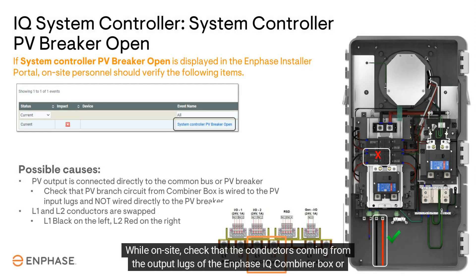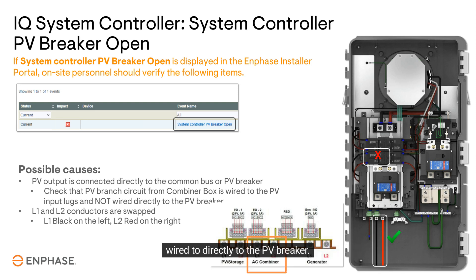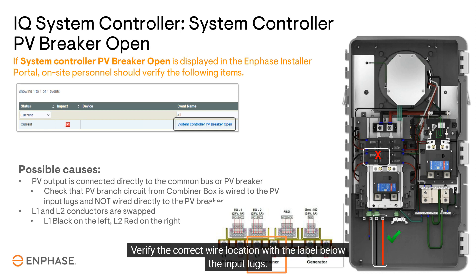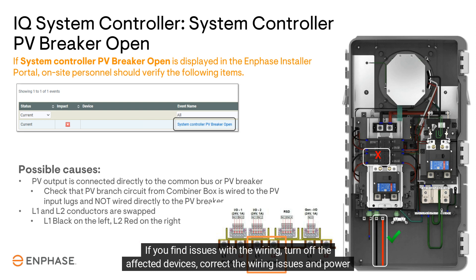While on site, check that the conductors coming from the output lugs of the Enphase IQ combiner box or your custom PV combiner box are wired to the PV input lugs at the bottom of the system controller, and not wired directly to the PV breaker. Verify the correct wire location with the label below the input lugs. If you find issues with the wiring, turn off the affected devices, correct the wiring issues, and power back on.